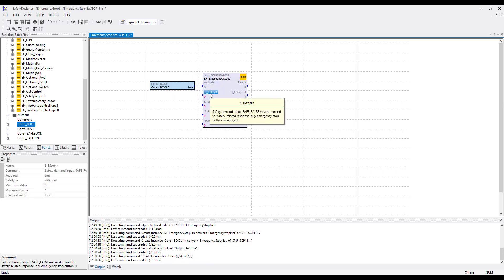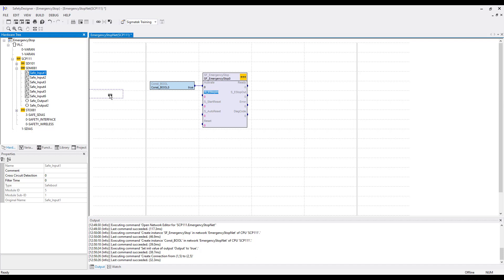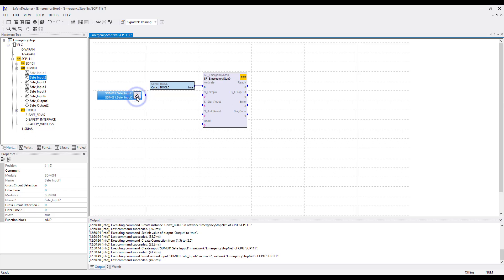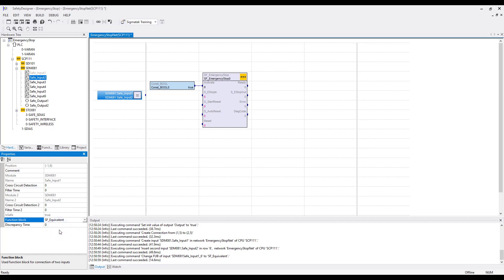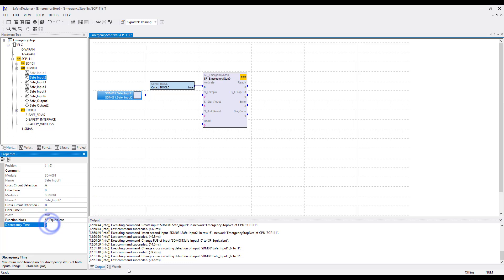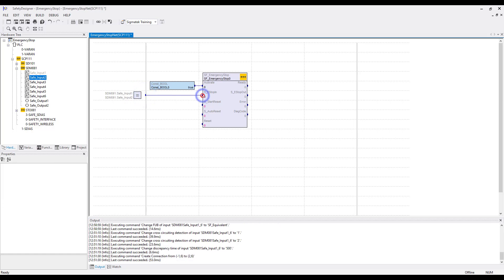For the E-Stop In we need the hardware. Go to the hardware tree to the module SDM081 and choose Input 1. Because of cross-circuit detection we also need Input 2, so drag Input 2 directly over Input 1. This creates a new function block. Click on this block and go to its properties. Set the function block to SF Equivalent. To set the cross-circuit detection, go to Cross-Circuit Detection and set A for Input 1 and B for Input 2. Set the discrepancy time. Then connect the inputs to the E-Stop In.